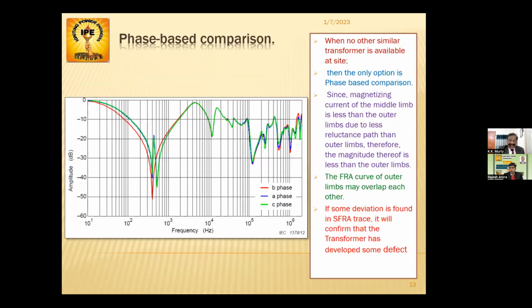So in that case, when no sister transformer is available, the only way is to verify the transformer's healthiness through its own phases. As you know, the A and C phase, by being in the outer limbs, will have similar characteristics since the reluctance path is the same for both outer limbs.